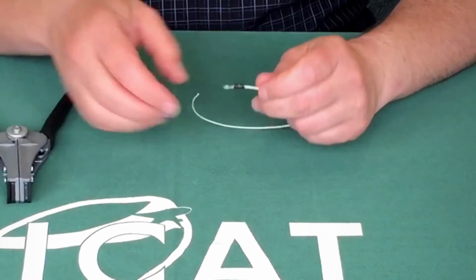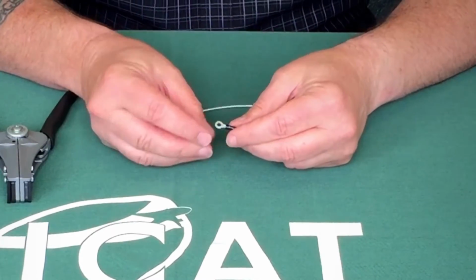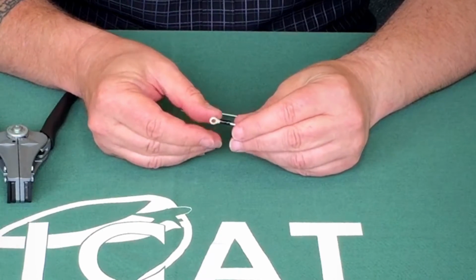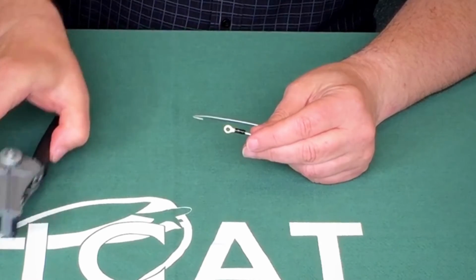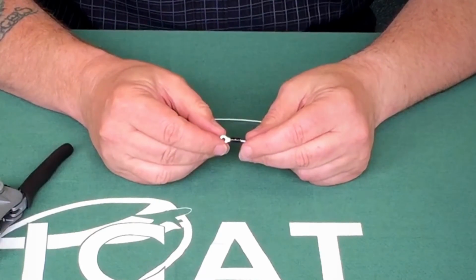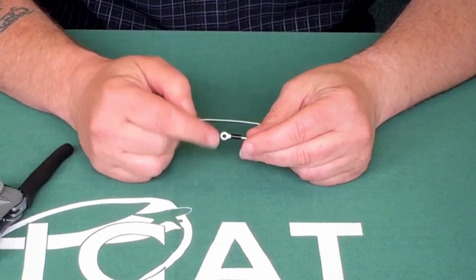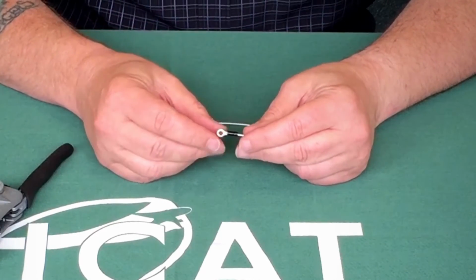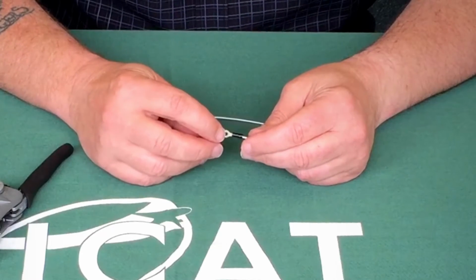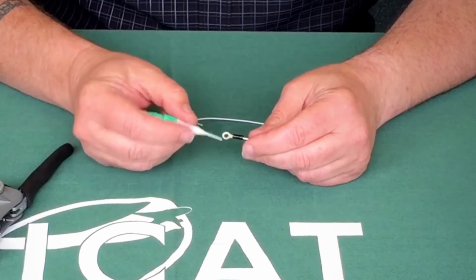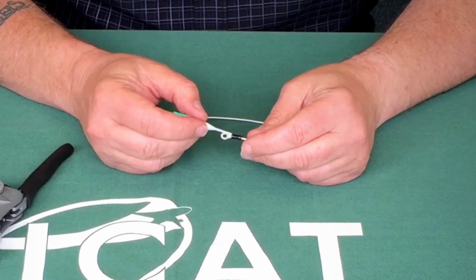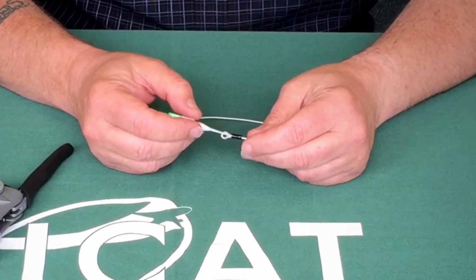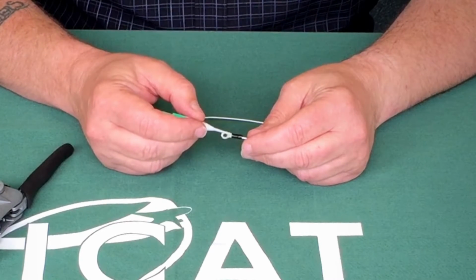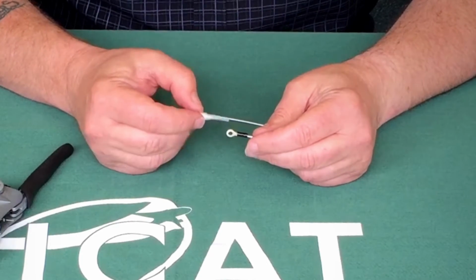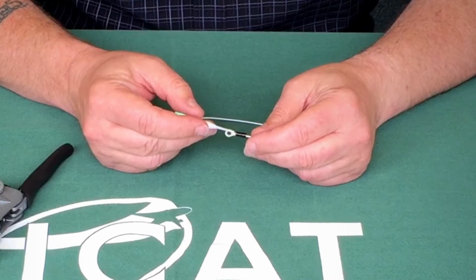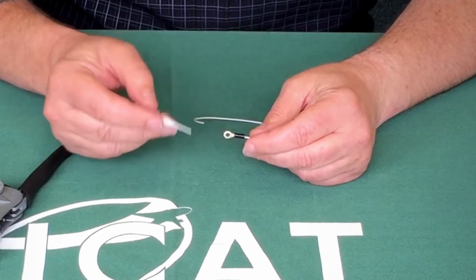So once I've stripped my cable, in this particular case, you put the connector or the crimp onto the stripped wire. Now, always, when you're using these, refer to the standard wiring practices manual. It will give you guidelines on how much conductor you should strip back for the particular connector. In this type of crimp, we should always see a little bit of the conductor protruding, as we can see here, from the edge of the crimp. The manual will typically tell you approximately between 1/64th to 1/32nd of an inch. Now that's incredibly difficult to measure, but it's generally accepted.